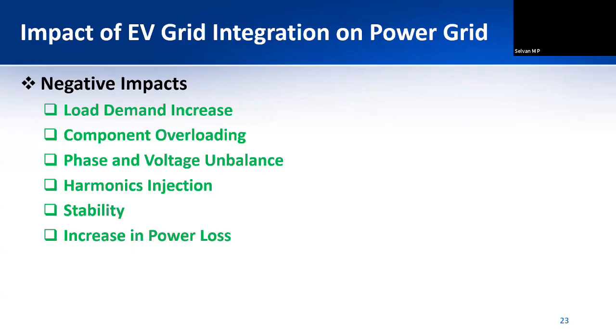Then when we have single phase charging, there may be a phase and voltage imbalance because single phase charging may not be balanced across all three phases of the distribution transformer, leading to unbalanced current since the current drawn for charging is more. That may lead to more unbalance than what is normally present in the distribution system. Distribution systems are designed to tackle a certain level of unbalance because we have many single phase loads, so neutral conductors are designed to cater for that. But if unbalance increases beyond the expected value, the neutral conductors cannot withstand the unbalanced current flowing through the neutral.